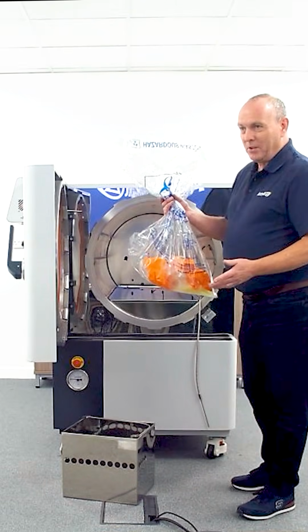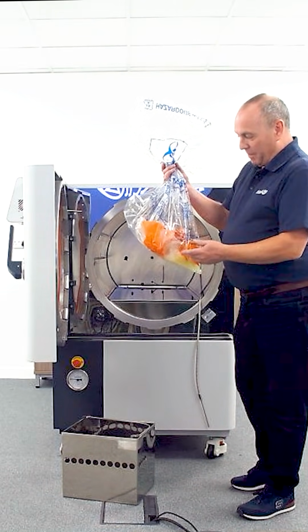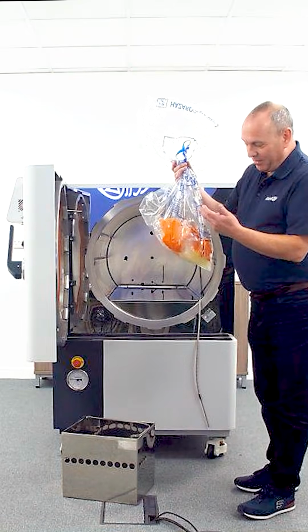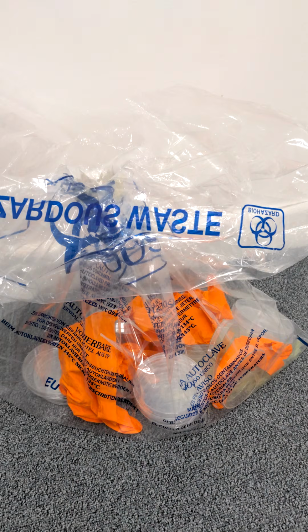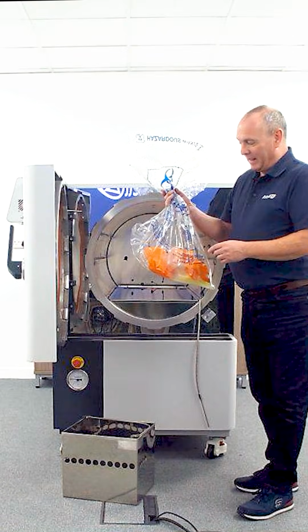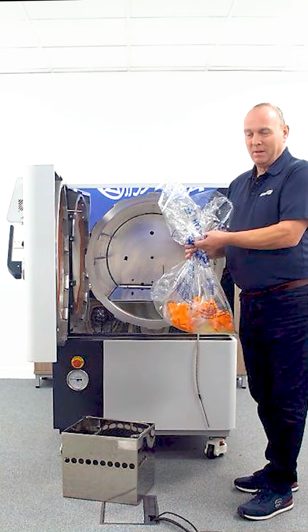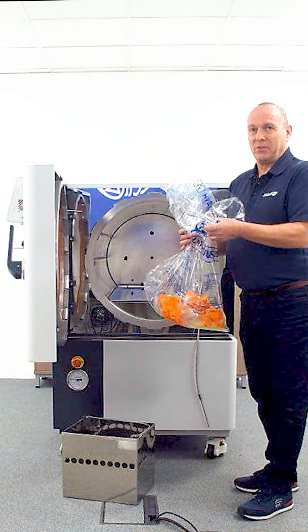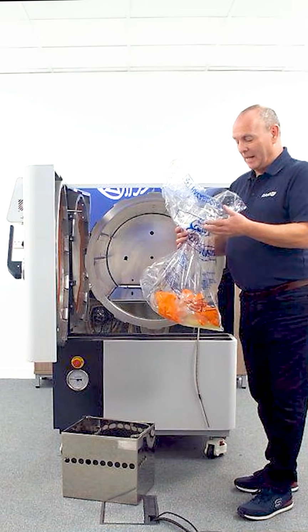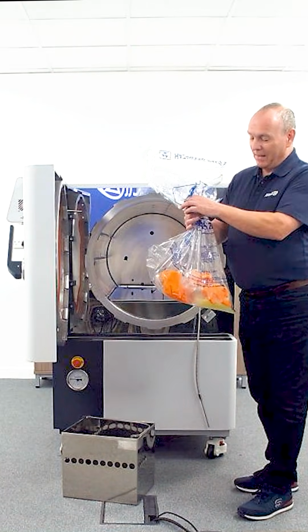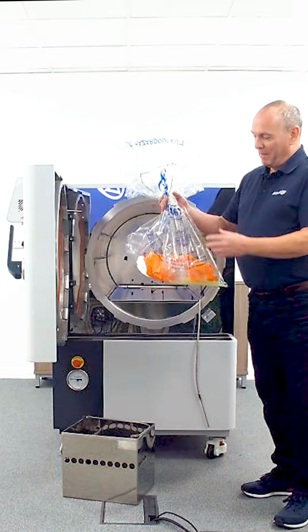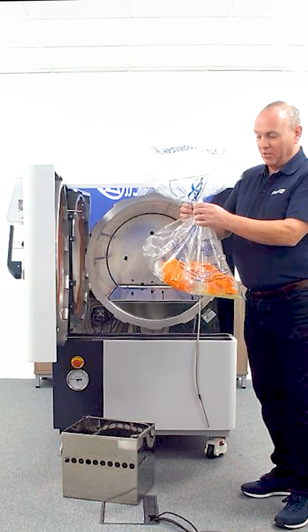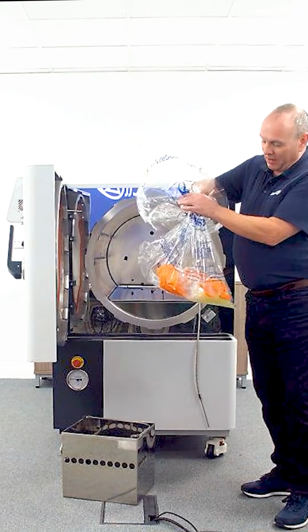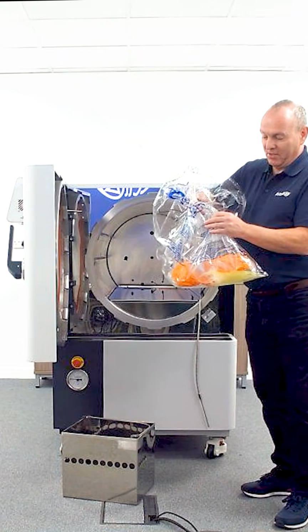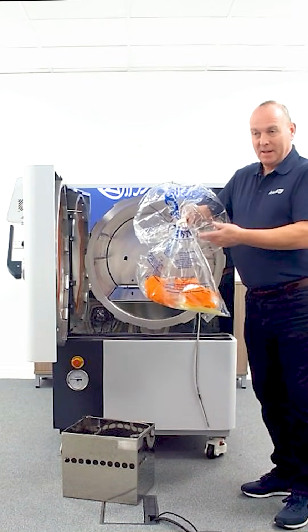For a discard load, a typical autoclave bag with a general load of Petri dishes, gloves, pipettes, anything general lab waste, tissues, could be anything in there. These bags should ideally be left open to allow the air to get out and the steam to get in. Or they could be loosely gathered and tied with autoclave tape just to keep the load together. The tape is up the outside, but it's still not completely tight. I can still get dust and fingers in there, so the air can get out of this bag.